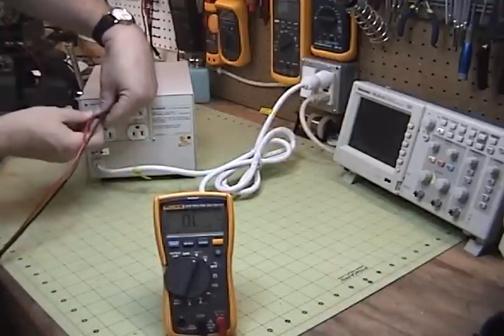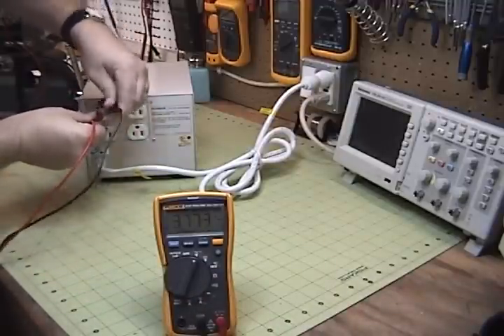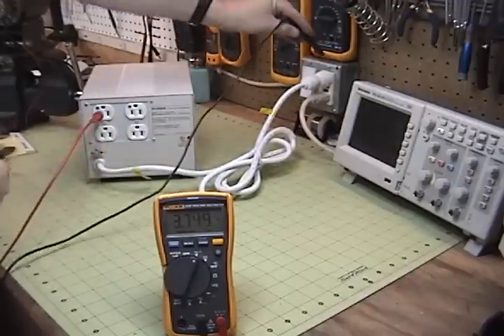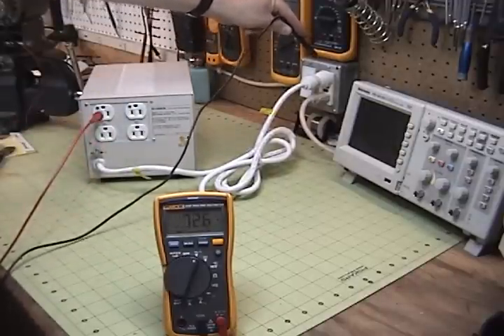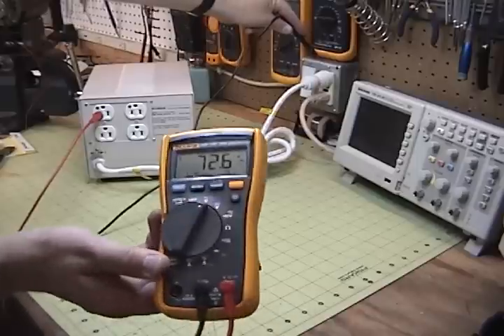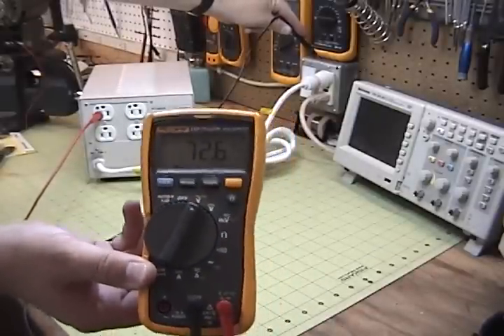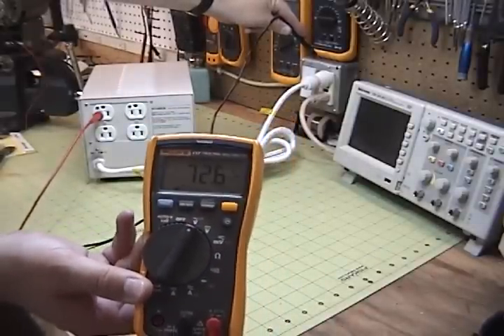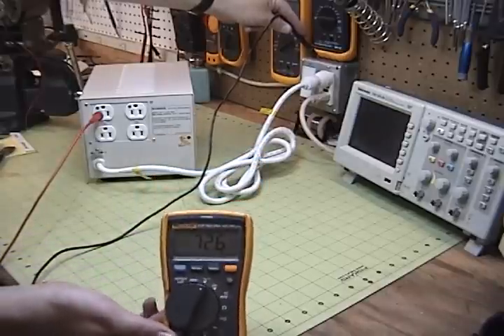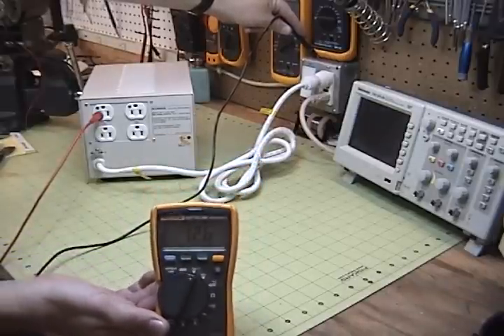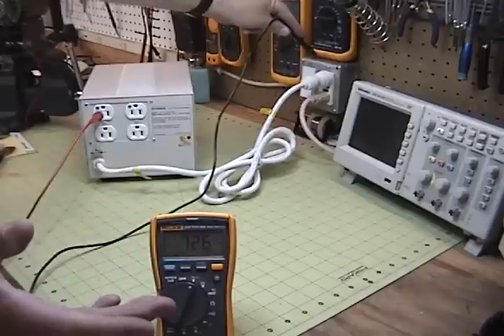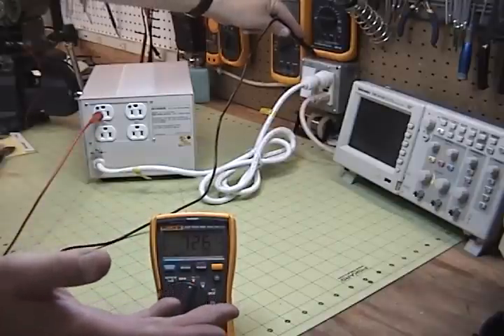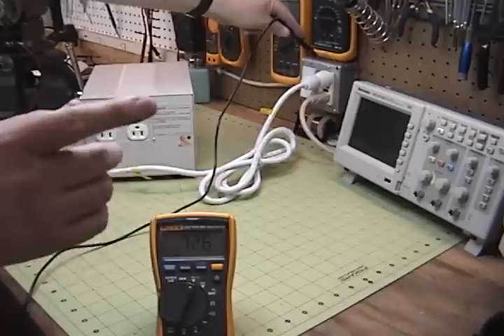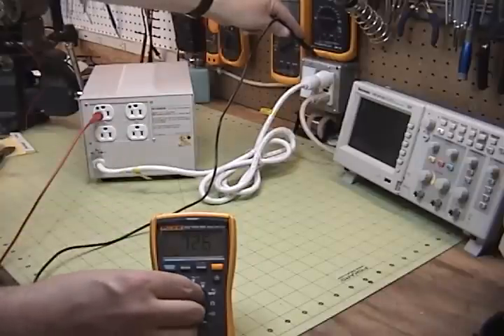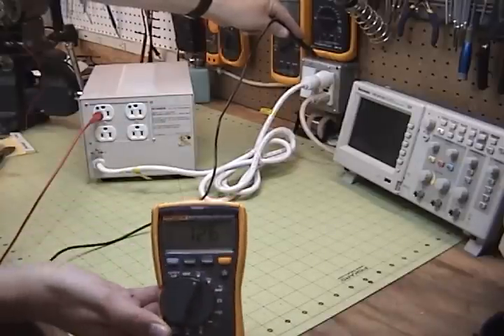Still with the alteration, I'm going to go over here, and this gets interesting. I'll touch the ground again with the fluke, and you can see you still get voltage. That's ghost voltage, being picked up across the lines. Essentially, it's a capacitance thing. We no longer have that strap going to ground for the secondary transformer, so we're going to pick up some voltage values, but they're not dangerous.